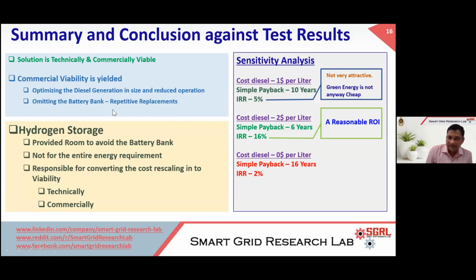When we come to the summary and conclusion of the test results, the solution is technically and commercially viable. The commercial viability is yielded basically by optimizing the sizing of the diesel generator and reducing its operation time. That means OPEX is drastically reduced by cutting fuel usage and increasing efficiency of operation, since the size rating of the generator is reduced. Maintenance of the generator is also reduced, further lowering OPEX.